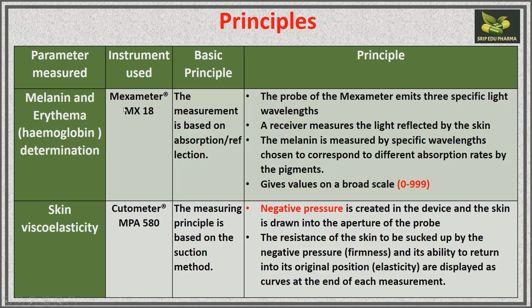For melanin and erythema (hemoglobin) determination, the instrument is the mexameter. The basic principle is absorption and reflection. The probe emits three specific light wavelengths, and a receiver measures the light reflected by the skin. Melanin is measured by specific wavelengths chosen to correspond to different absorption rates by the pigments. Values range from 0 to 999.